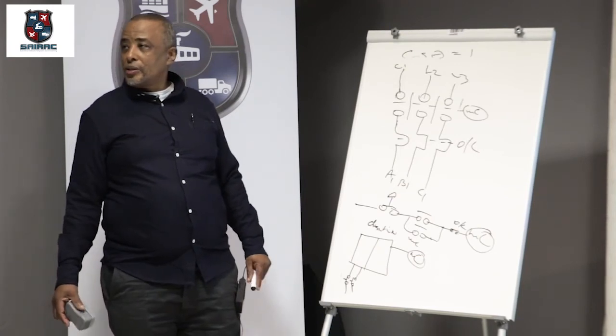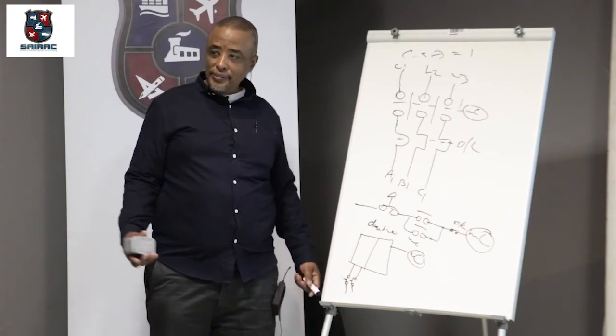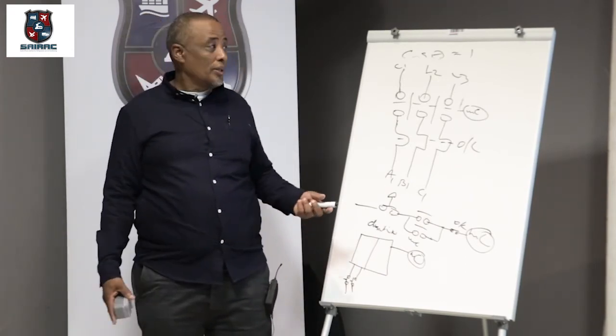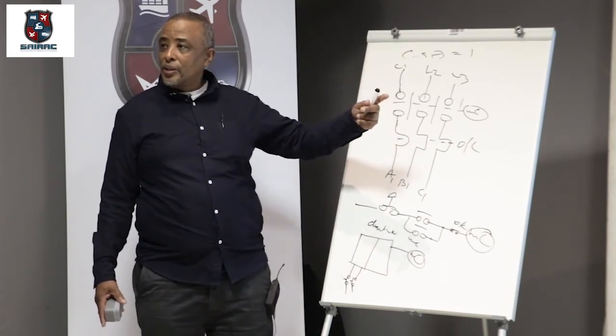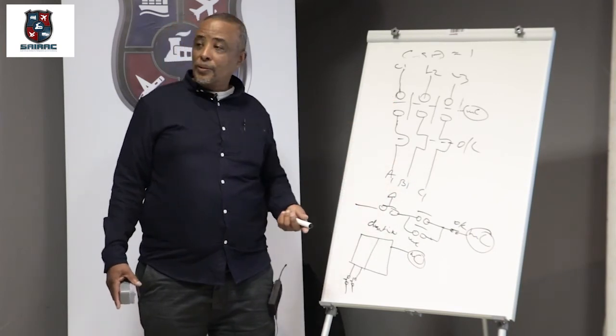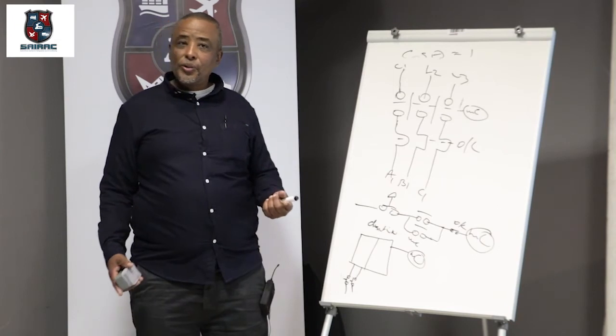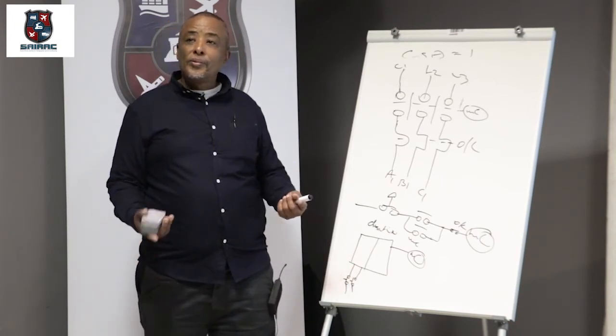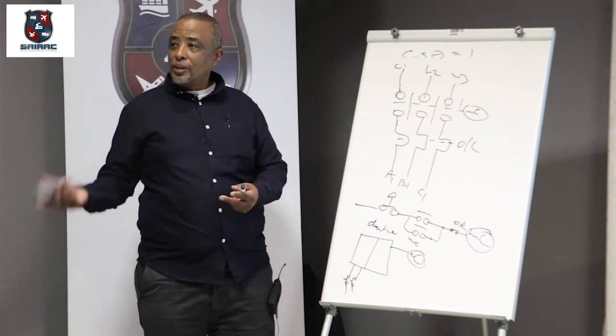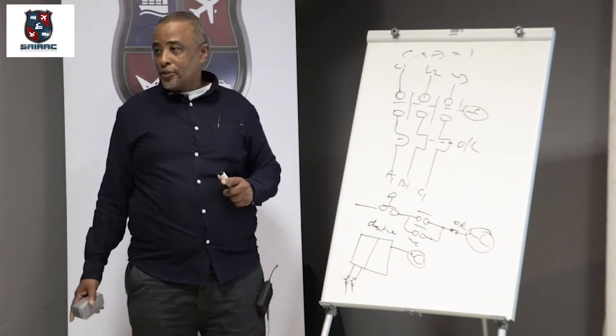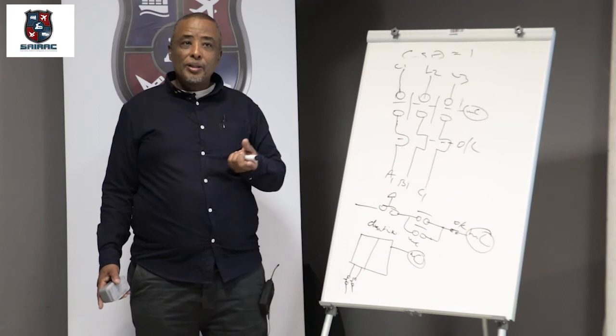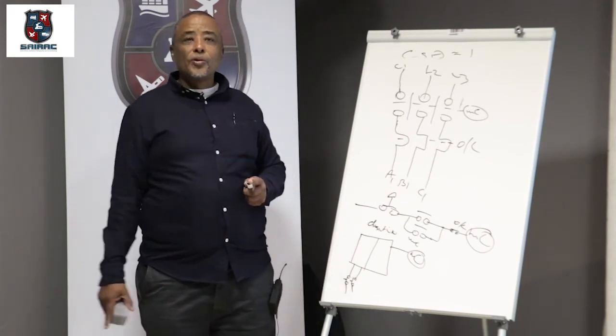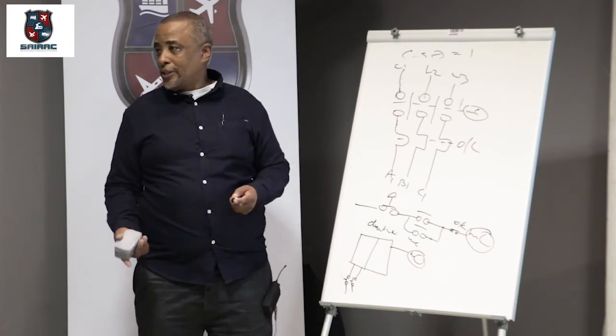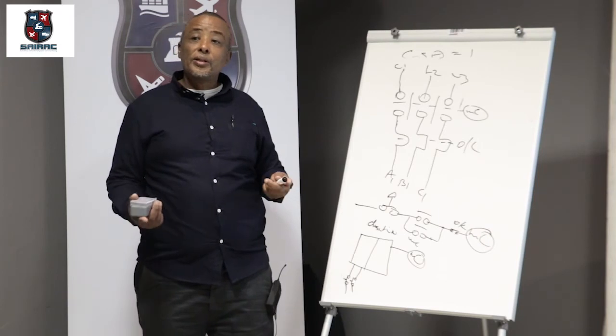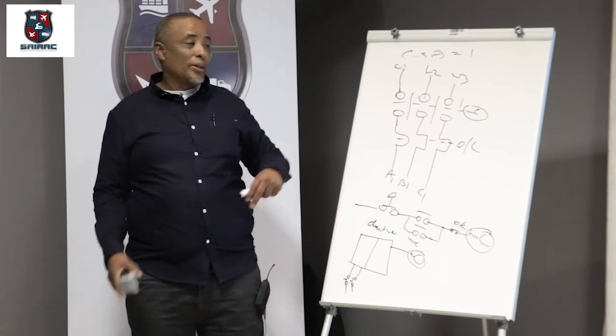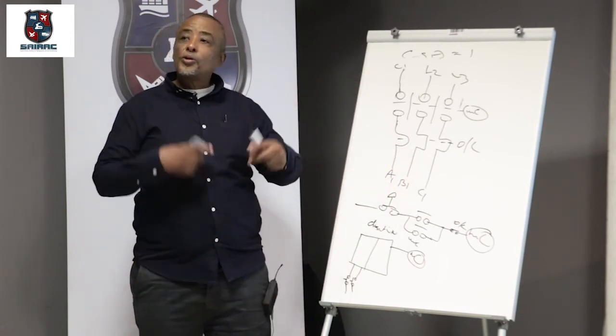Question, those who have done N3, they always ask, are three-phase motors self-starting? The answer is yes, three-phase motors are self-starting because of the rotating magnetic field. Are single-phase motors self-starting? The answer is no, because you have two windings, a start winding and a run winding. The start winding runs, cuts out, and the run winding comes in. But what creates that phase shift? An addition of something external, a capacitor. The capacitor creates that phase shift, and this is how the motor starts. Without a capacitor, when the motor capacitor packs up, it won't start. So they need to add something to the circuit to create that phase shift.